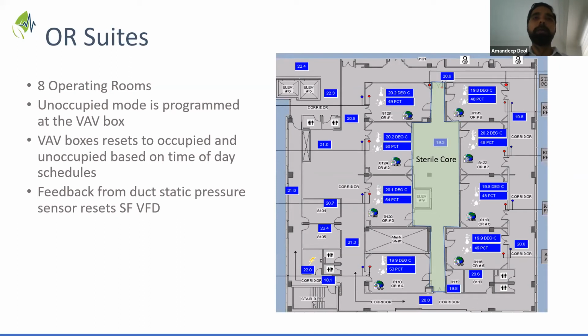Currently, the unoccupied mode is programmed at the VAV boxes. So basically, the way it works is the VAV boxes reset to occupied and unoccupied mode depending upon the time of day schedule. This is slightly different from another case study where they use actual occupancy in the room. The fan basically resets the VFD based on, once the box is closed in unoccupied mode, the pressure builds up and the fan resets the VFD based on the static pressure sensor.